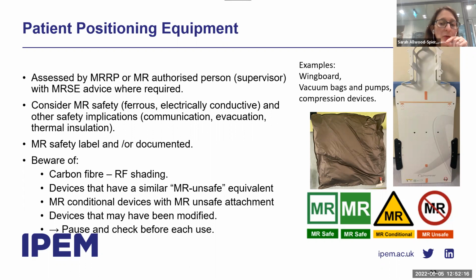But examples of equipment that might be used for positioning the patient include a wing board, vac bag, compression devices. These must be assessed by the MR responsible person with MR safety expert advice if required. They will consider the typical MRI safety. Is this ferromagnetic? Is it electrically conductive? But also the other safety implications. Does it hinder communication for the patient? Does it make evacuation of the patient from the scanner more difficult?